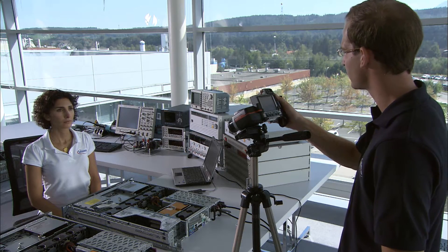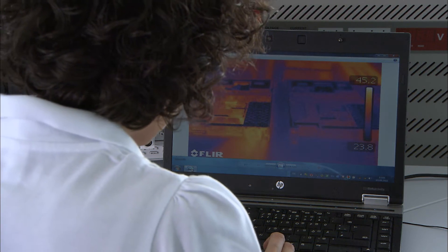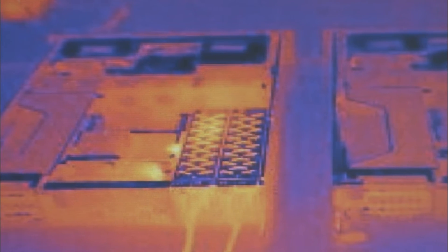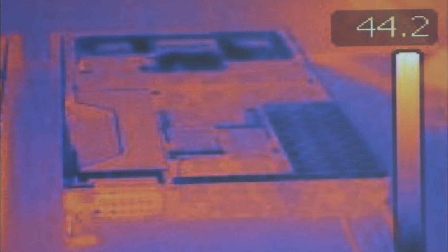An infrared camera documents the results. The camera shows that the power pack with conventional silicon chips produces considerably more heat than the power supply equipped with semiconductor chips made of silicon carbide. According to our measurement results, we expect higher efficiency in the server and therefore less energy consumption in the server farm.